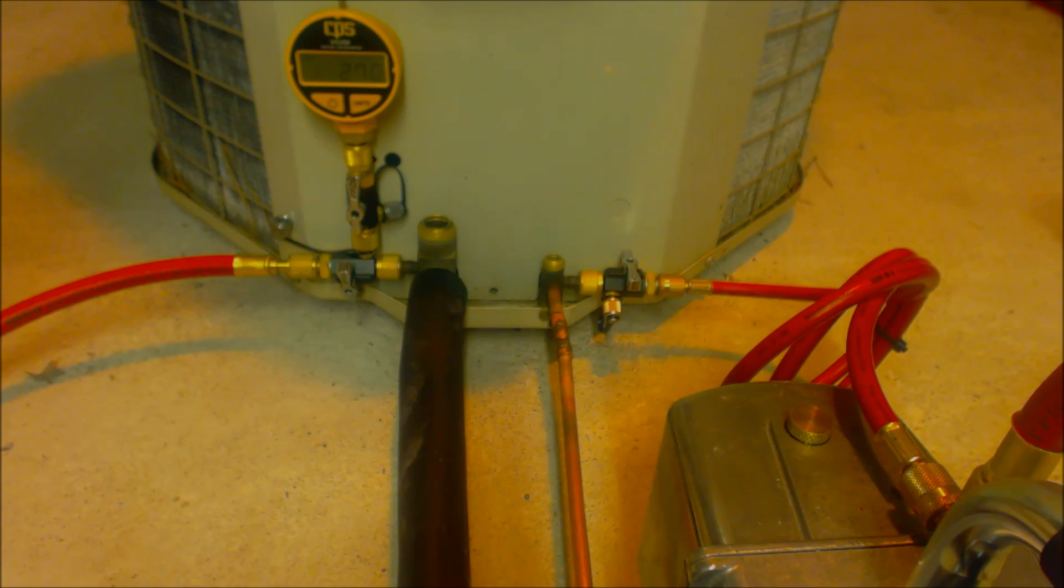Okay, the micron gauge stopped moving and it seems to be holding steady at 270 microns. It's been about eight or nine minutes, something like that. You want to just test the micron level for about five to ten minutes just to make sure that it's not going up.